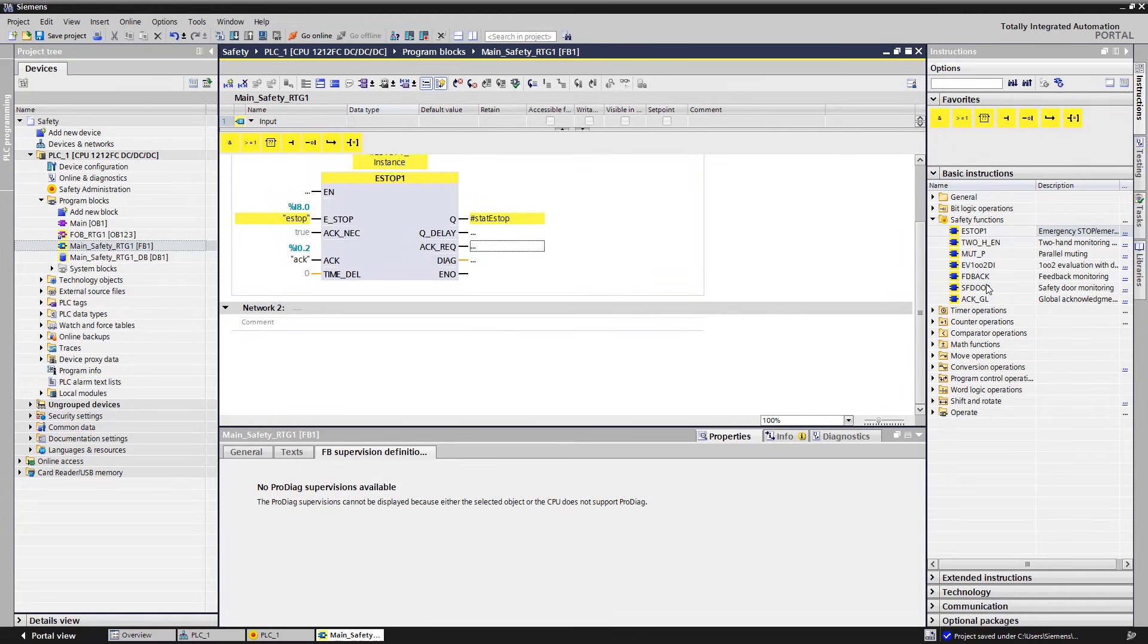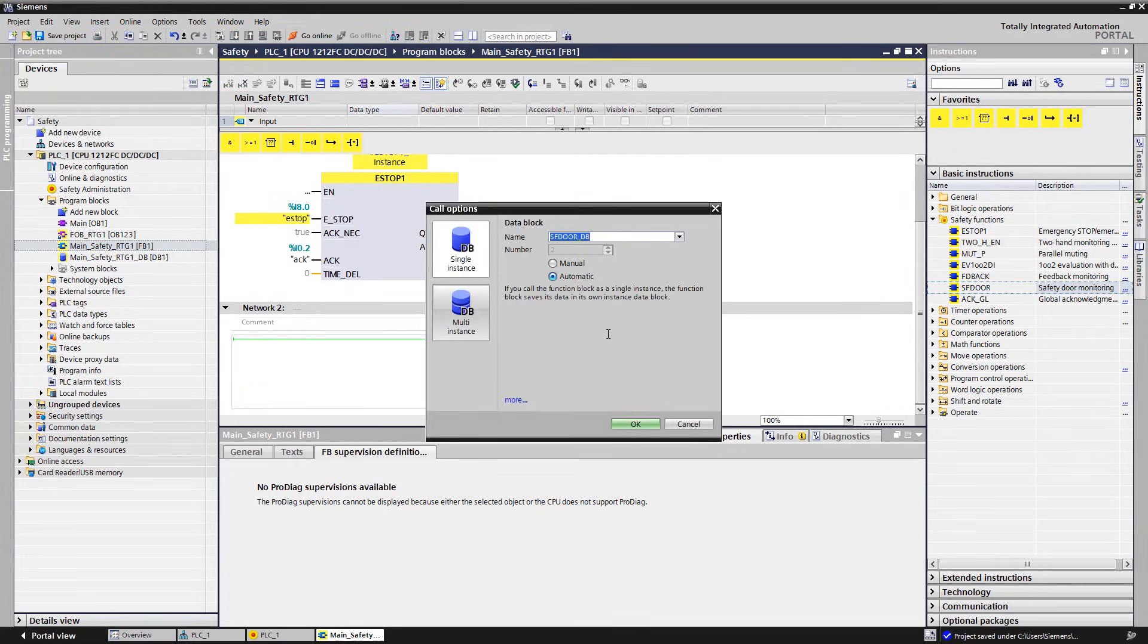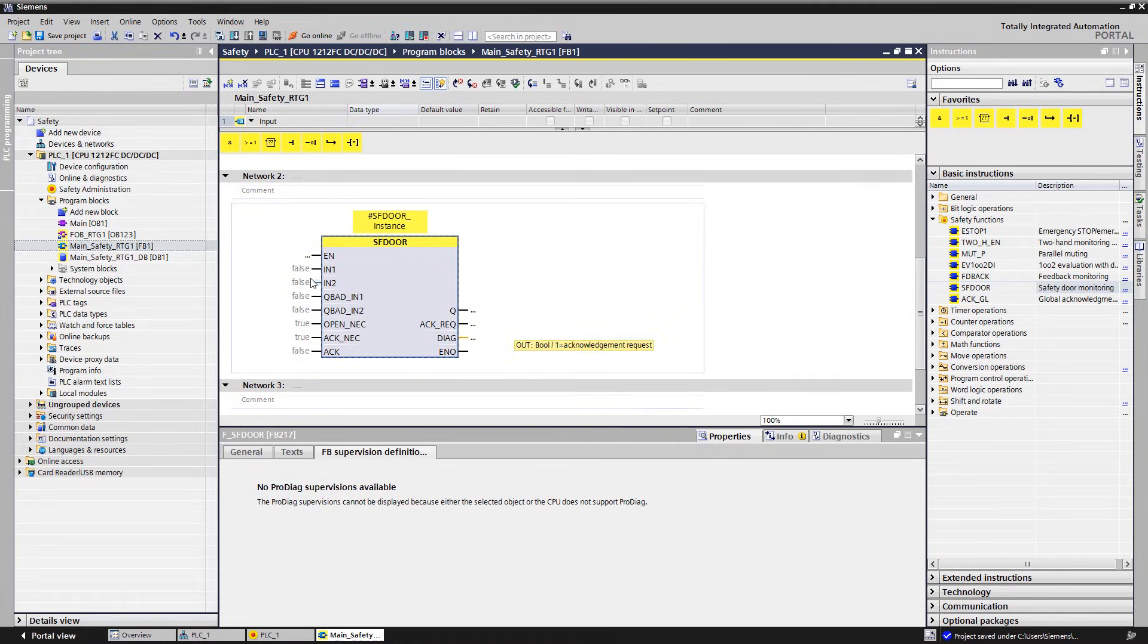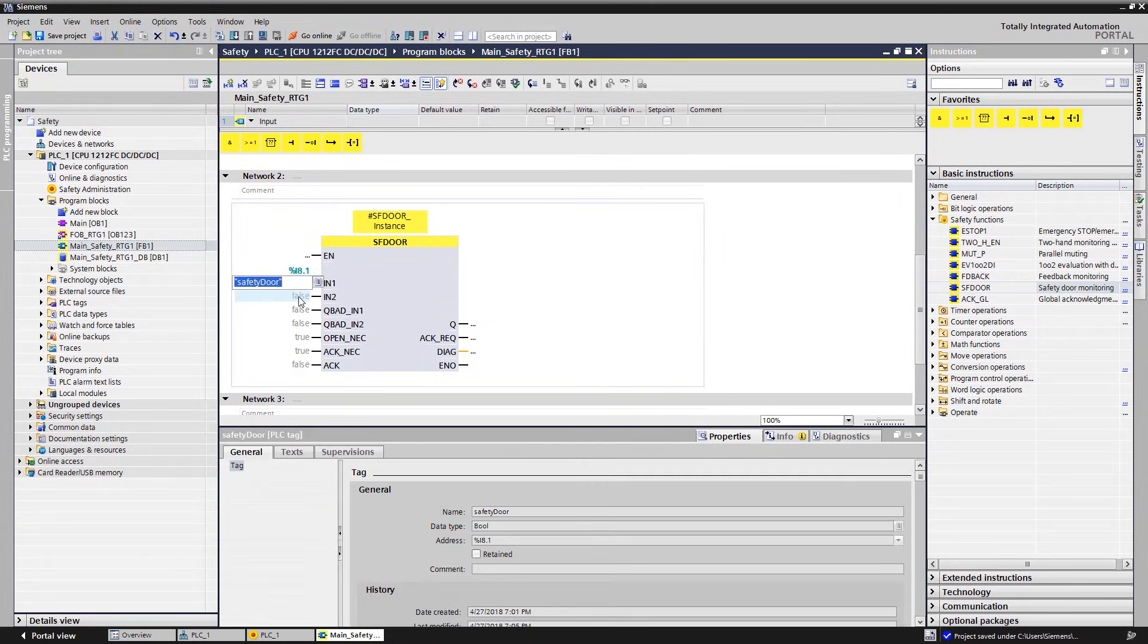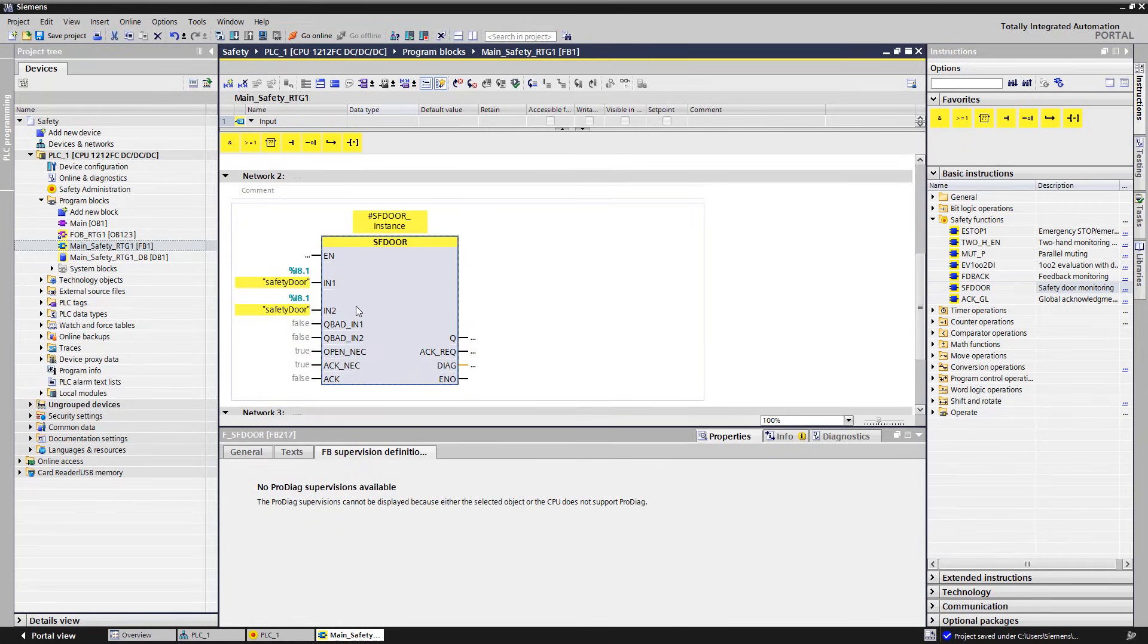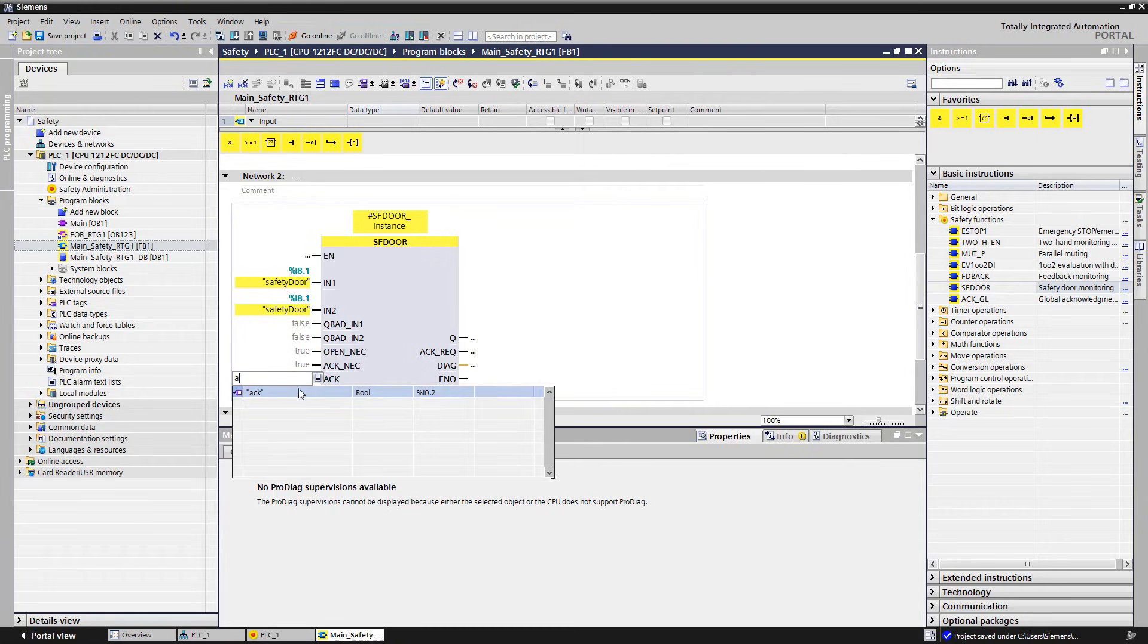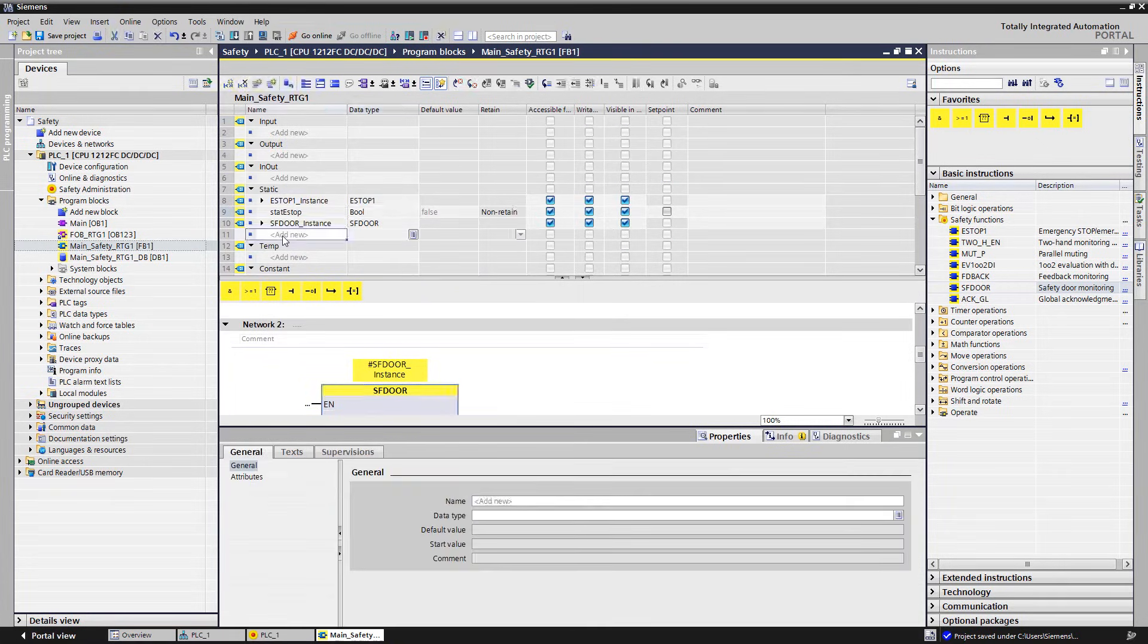In the next network, we drag the block for the evaluation of the safety door. We connect the two block inputs, each one with a variable safety door, since our protection monitor contains only one safety position switch. The functionality of the ACK NEC input is identical to our e-stop module. Again, we need the acknowledgement and a static variable, which we will later use for the connection.